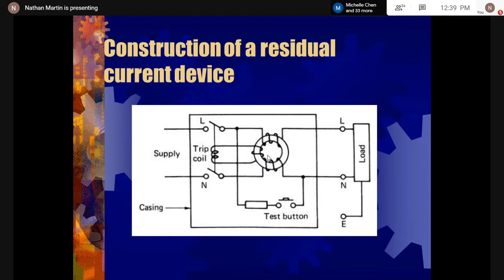And if they are of different magnitude, we are going to have a voltage difference. So we are going to have a resultant developing, and this resultant will cause an induced voltage in the trip coil. You see the trip winding, we're going to have an induced voltage, and because the trip winding goes to a coil that is continuous, we have a closed path for current to flow. A current will flow, and a coil around a shaft is basically a solenoid, and the breaker and the switches in the device will operate. Simple operation.